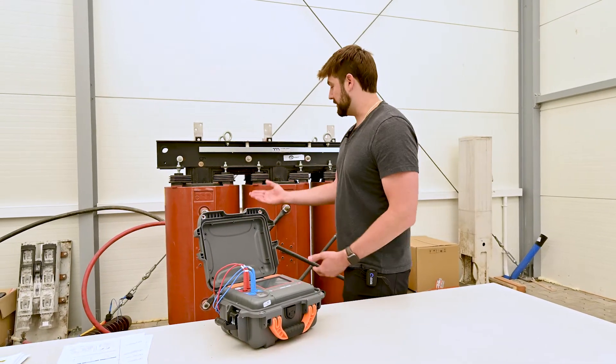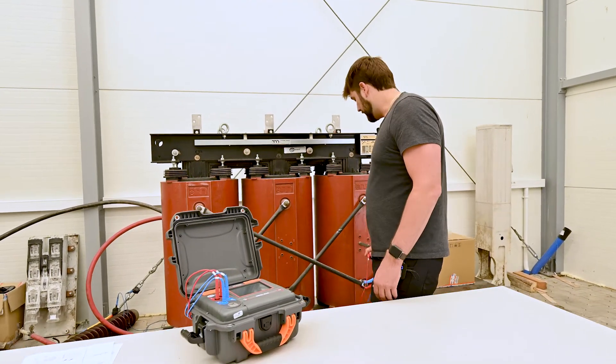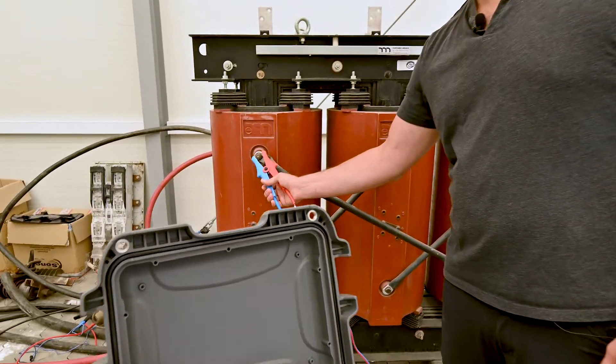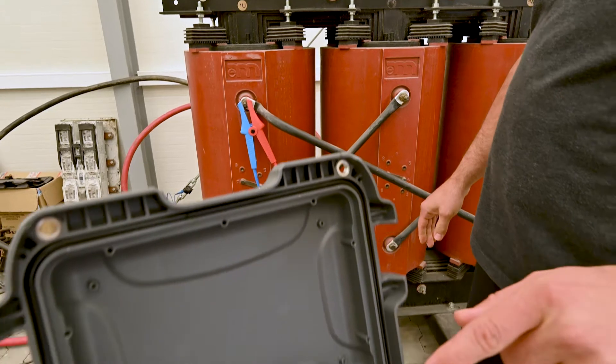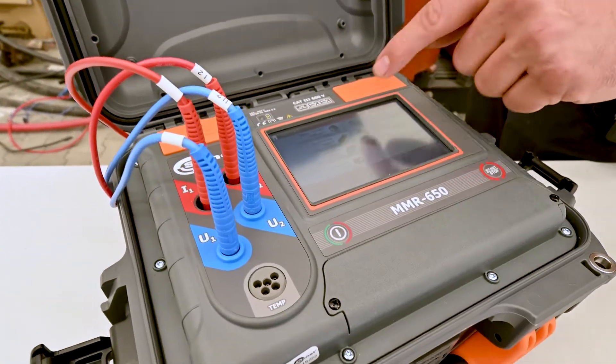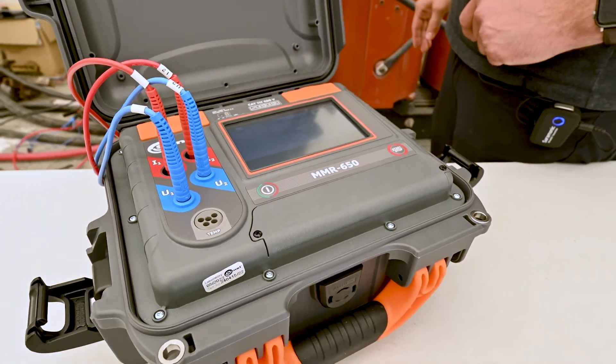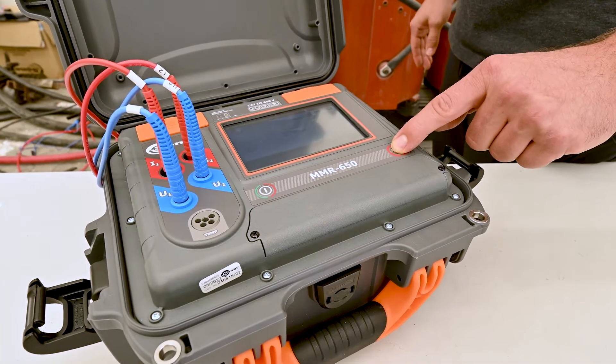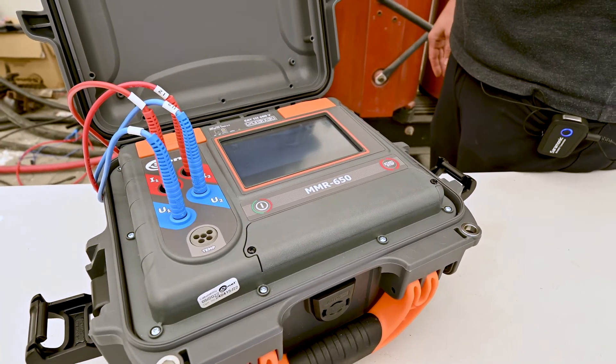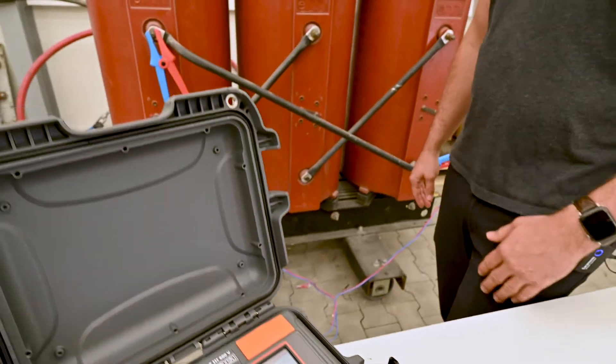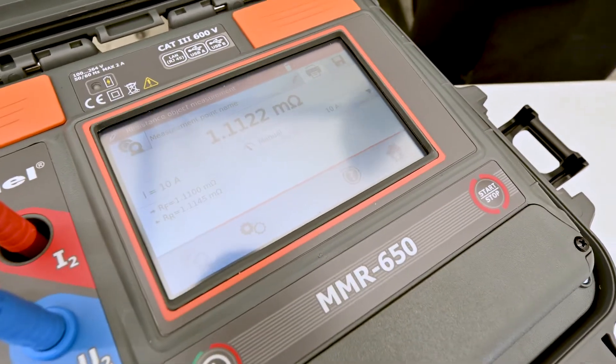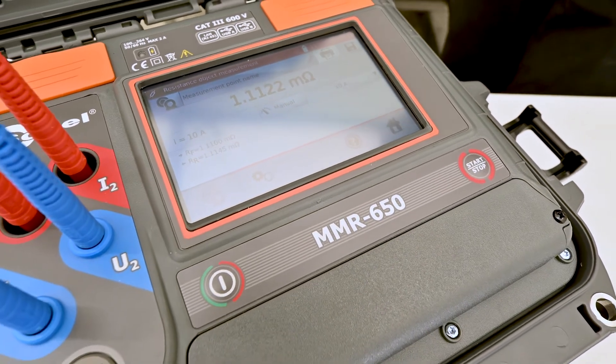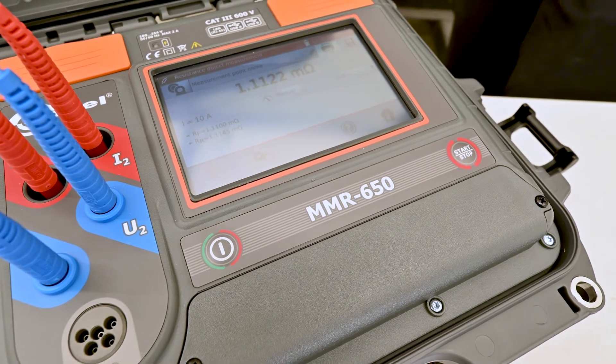So if I want to know the resistance of this jumper, I can just move across to here and I'm going to select resistance object measurement. The test should be much faster. There it is, 1.1 milliohms. Much faster when you're just going through a nice conductor that doesn't have a big coil.